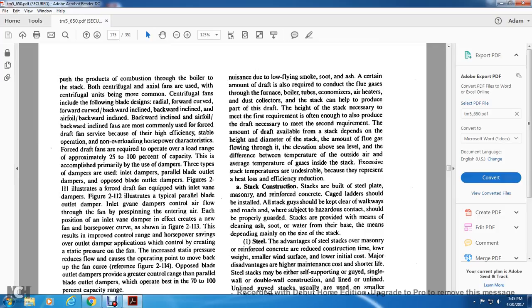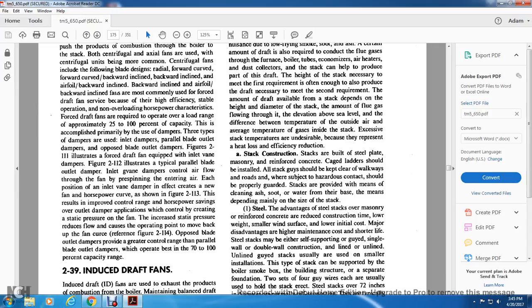The stack can help produce part of the draft. The height of the stack necessary to meet the first requirement is often enough to also produce the draft necessary to meet the second requirement. The amount of draft available from the stack depends on the height and diameter of the stack, the amount of flue gas flowing through it, the elevation above sea level, and the difference between the temperature of the outside air and the average temperature of the gas inside the stack. Excessive stack temperatures are undesirable because they represent heat loss and a reduction in efficiency.